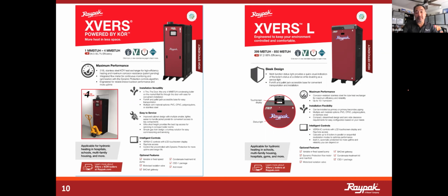The other thing about this is if they are cascaded together, and the master, you say that you're running on one boiler, if the system is calling for additional heat, the master will not allow the second heater to come on unless there's adequate flow for the second heater. That's probably the number one cause of failure in multiple boiler systems: when the second boiler comes on, if there's no way to monitor what the total flow is, and all of a sudden you're splitting the flow in half because you have two boilers fired, that's when you see your greatest stresses on the heat exchanger.